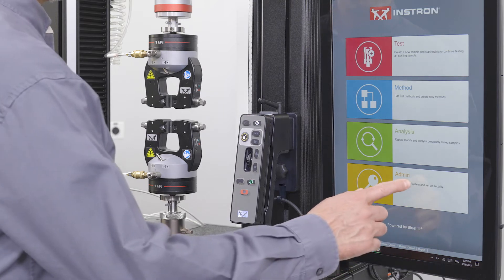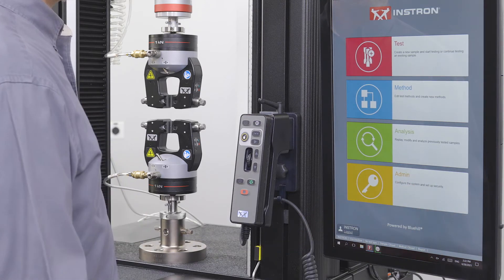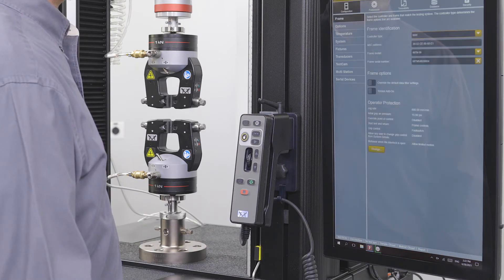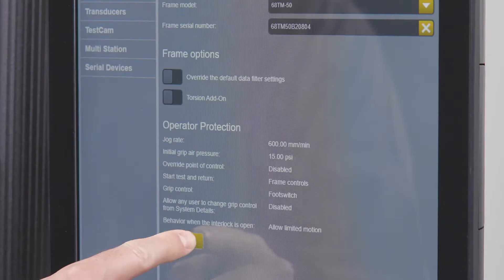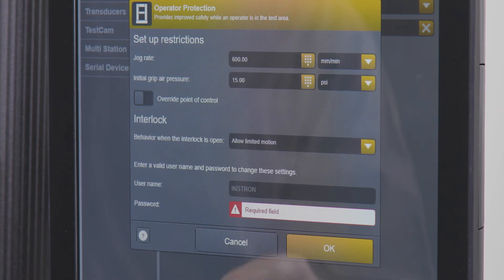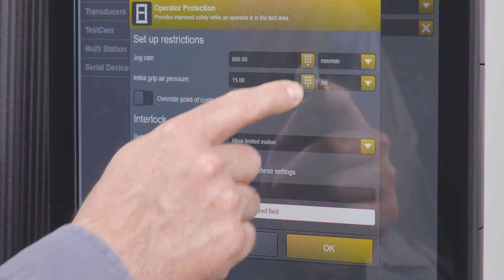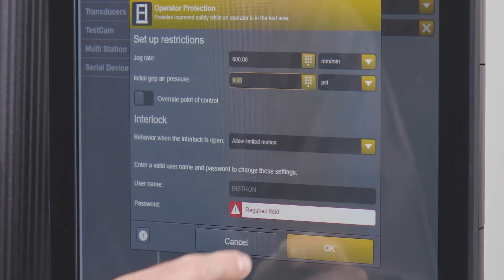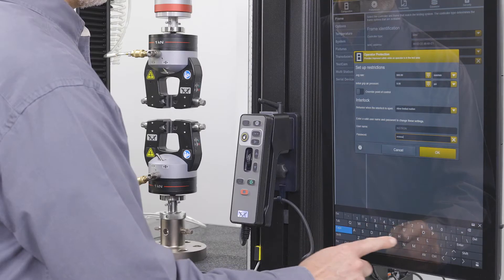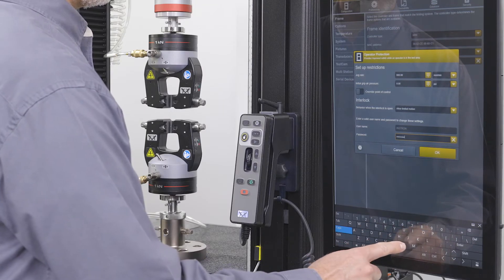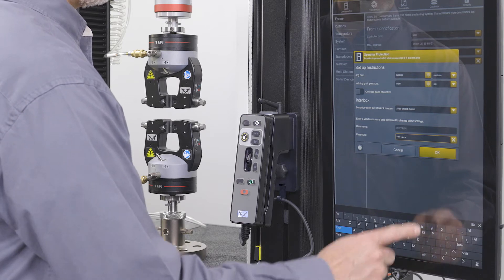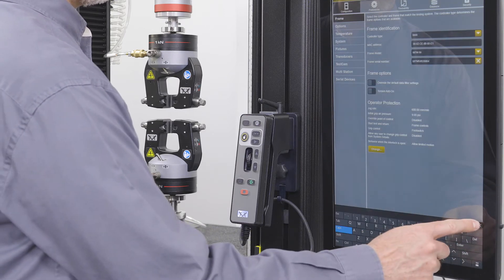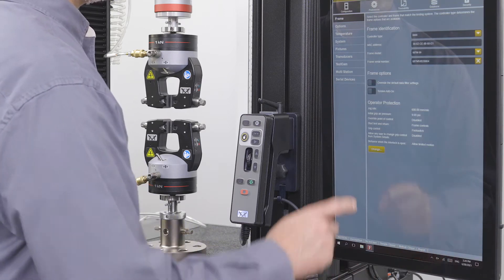The default initial setup pressure can be adjusted in the administrator portal in Bluehill Universal. The setup pressure should be the minimum pressure required in order to clamp your specimens. Your Instron service engineer can set this for you during the installation.